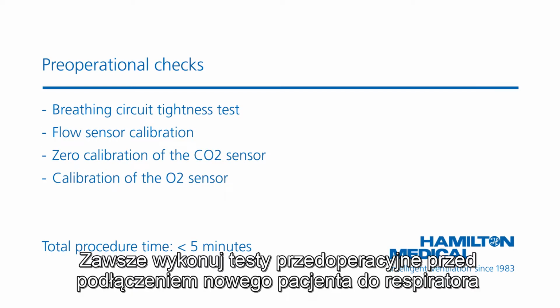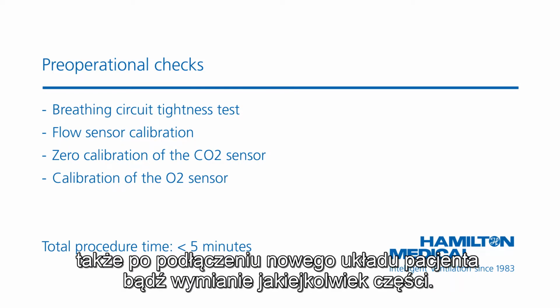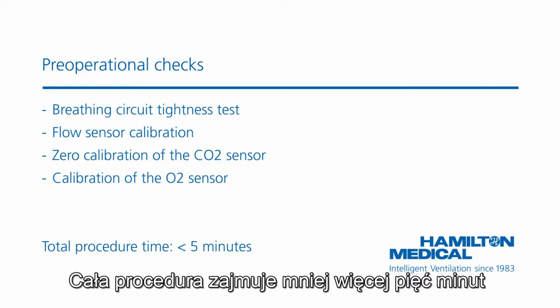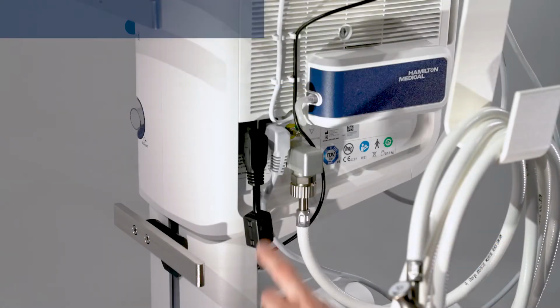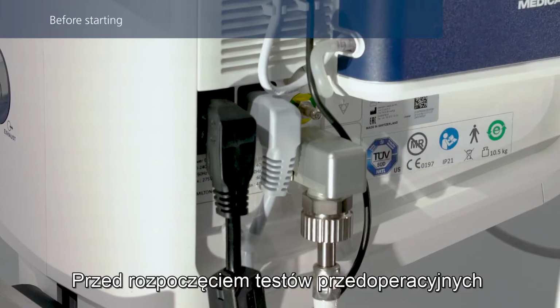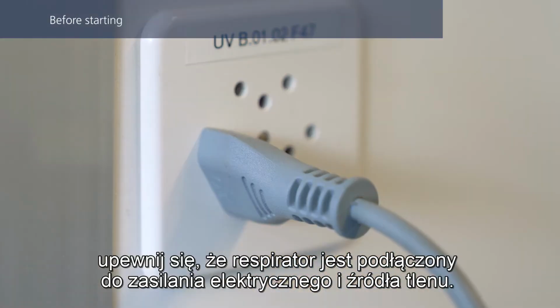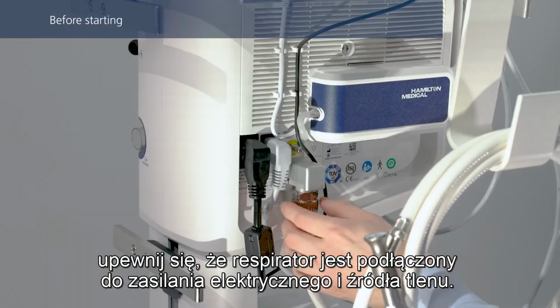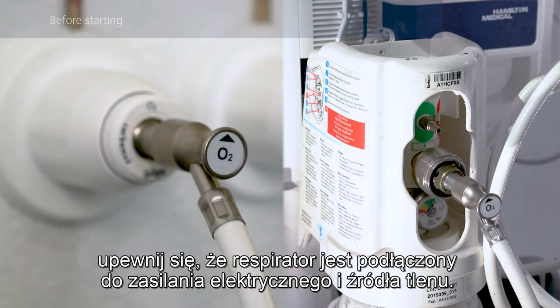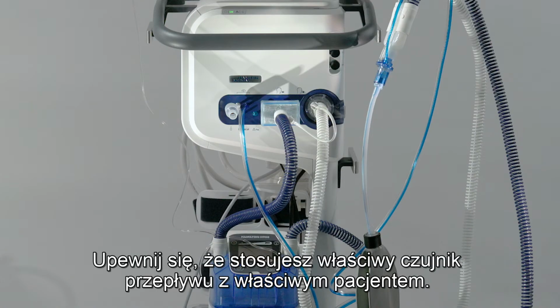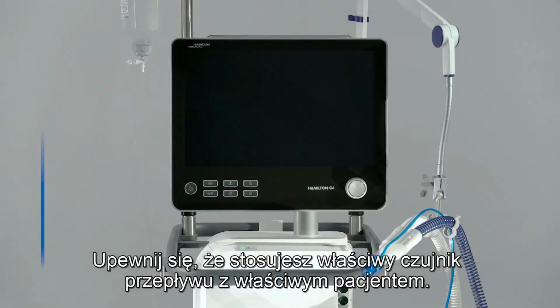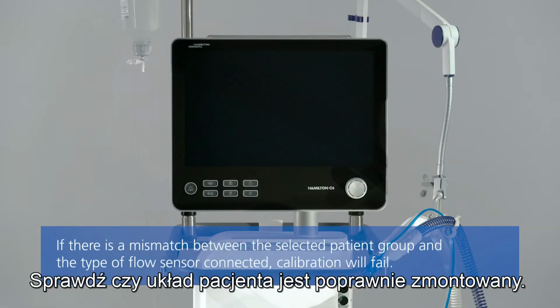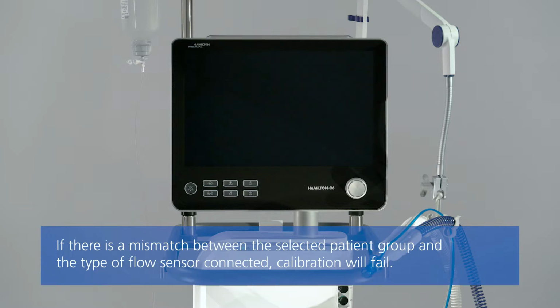Always run the pre-operational checks before connecting a new patient to the ventilator and after connecting a new breathing circuit or any new component. The whole procedure takes approximately 5 minutes. Before starting with the pre-operational checks, ensure that the ventilator is connected to both primary power and an oxygen supply. Ensure you are using the correct flow sensor for the patient. Verify that the breathing circuit is assembled correctly.